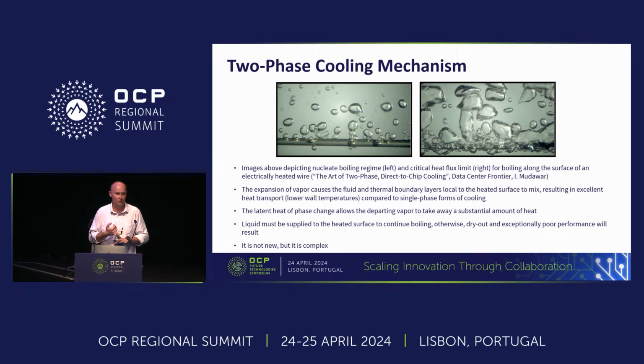The other benefit of two-phase cooling is that when you remove heat, you're using the latent heat of vaporization. So ultimately we don't need as much fluid to remove the same quantity of heat as you would with a sensible-heat-based technology such as single-phase water, single-phase dielectric, or single-phase immersion.